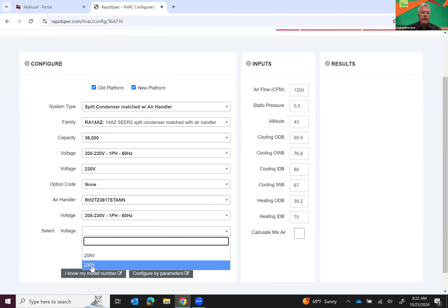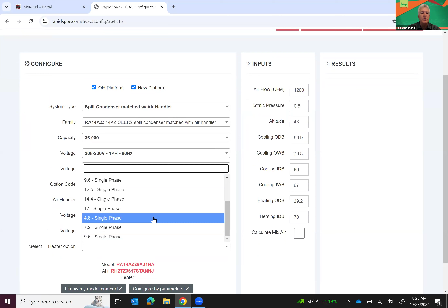Heater option—I wish they would do this a little better, but they don't. You'll notice these single phase options here, and as we scroll down, different options. If we select this one, the part number listed is an RXBH 1724A10J. That 'A' designates whether or not it has a pull-out disconnect or circuit breaker, or if it comes with no circuit breaker or disconnect.